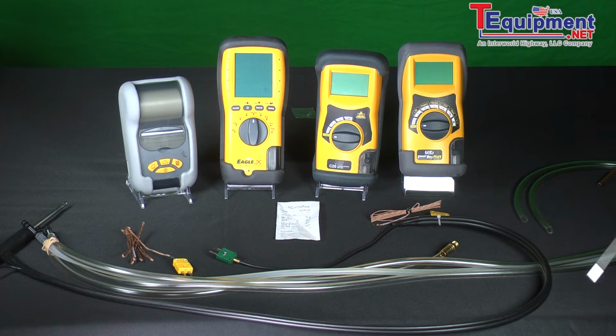One of the unique things too on the cracked heat exchanger test is it's one of the few tests where you can print out to show the customer that there is a crack in the heat exchanger. Basically what happens is you take a reading before the fan comes on, and then after the fan comes on about a minute, you take another reading. If you see an increase in the oxygen content by 0.5% or more, you know that you've got a cracked heat exchanger. The printout shows you the before, the after, and subtracts the difference in the oxygen reading so you can show your customer. And again, as I mentioned, we have a separate printout for each of the tests.